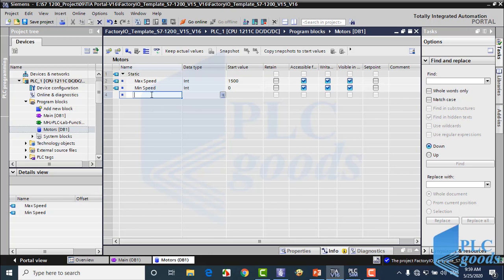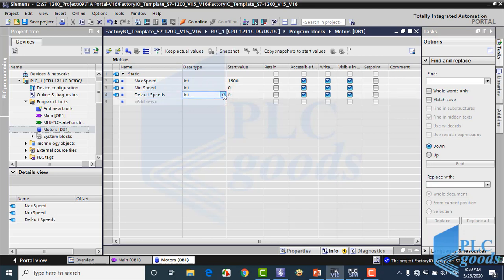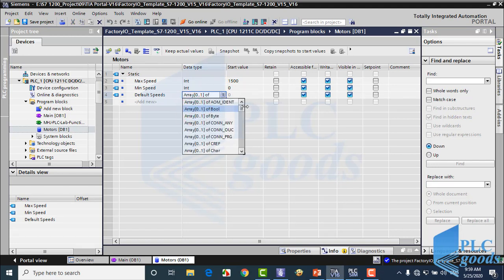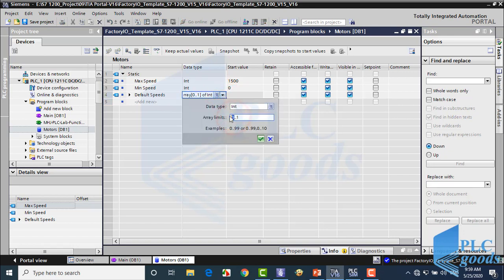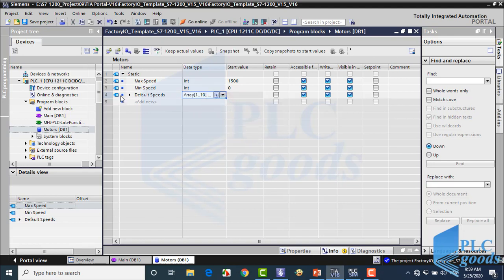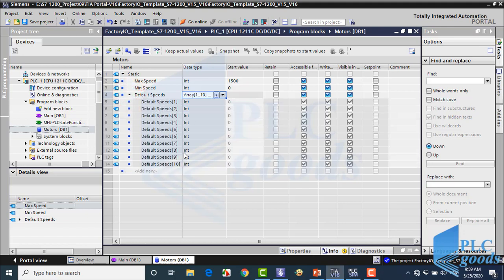I want to explain a useful way to define similar data. Suppose you have 10 or 100 similar motors. I would have to define 10 or 100 tags for their default speeds. Here, with array structure, we can define them easily. At this column, select array, then select the data type. Then determine the number of your motors — I select number 1 to 10. Now I can write a default speed for each motor.